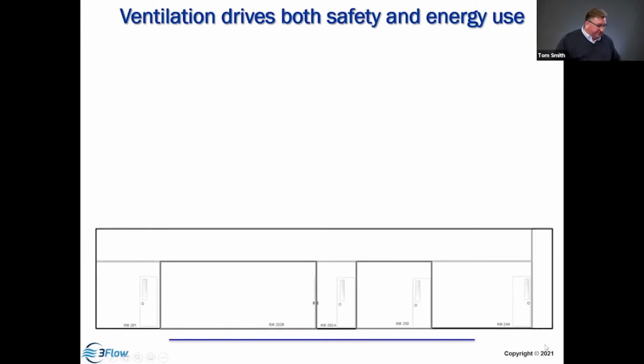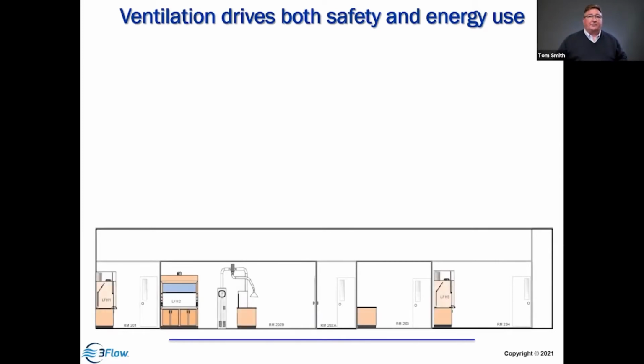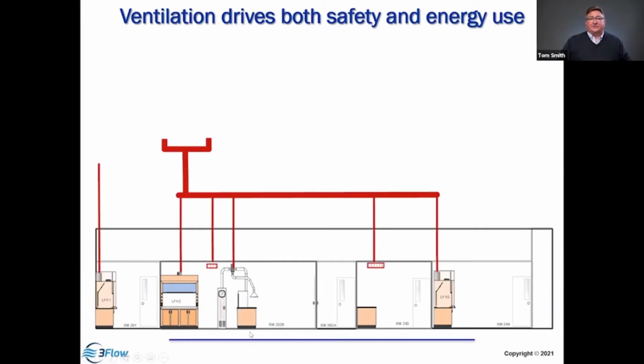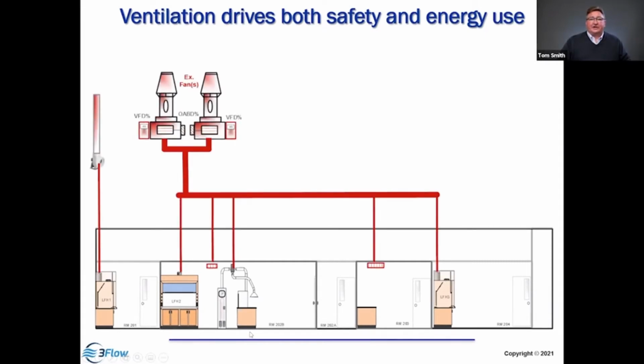So let's build up a system. If we're operating a system, we first add some walls, and in that we're going to populate it with some hoods. So we've got some fume hoods and some local exhaust ventilation, but we've got to get those materials out of the building, so we're going to add some exhaust ducts and exhaust fans. So we have a single hood, single fan system, and we've got a manifolded system, multiple hoods connected to an arrangement of fans. But we've got to balance the flow. So let's put in some dampers. Now we've got dampers that can control and balance the airflow between the different devices.